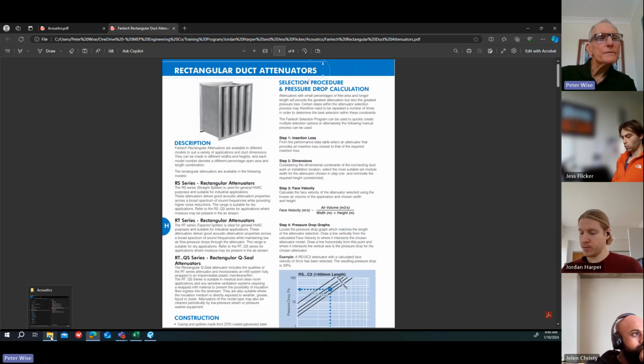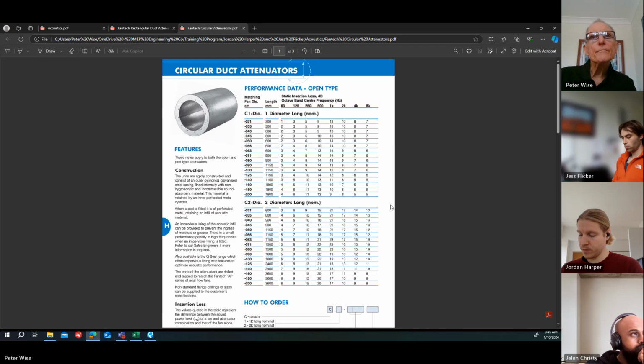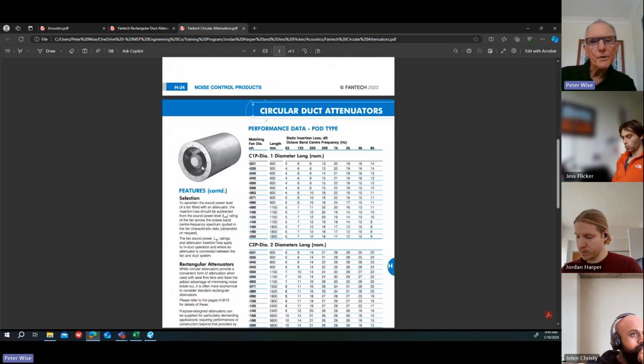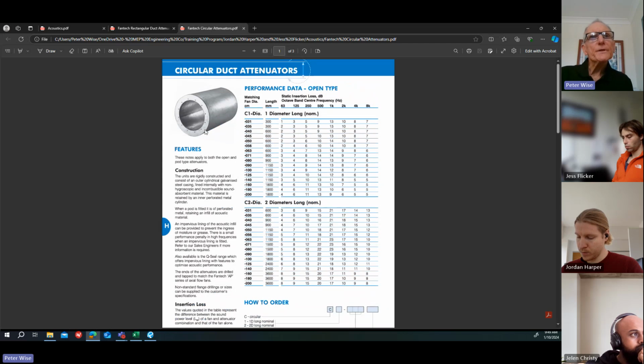Now, the other one is the circular attenuators. So you can have just a cylinder, an open cylinder, or you can have the cylinder with a pod in the middle. The open circular one comes in either nominal one diameter length or 2 diameters length. You don't get much attenuation from these attenuators because basically that's just a piece of duct, but it's basically internally lined duct. The insulation thickness is usually about 100 millimeters, so it's better than a piece of duct with internal insulation, but doesn't give you a great amount of attenuation. These are commonly used at the inlet and outlet of axial fans, and because it's basically a duct, they can be bolted directly onto the fan without affecting the fan performance.